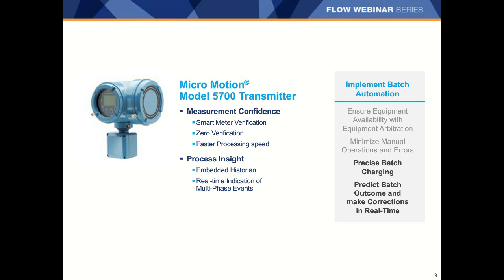The 5700 also offers faster, cleaner transmission of data. When milliseconds count in your fast control applications, signal speed and resolution are key. The 5700, that's the new high bar for providing the fastest response time and over 3 decades of knowledge in Coriolis signal processing to react quicker than ever in dynamic processes like batching and fluctuating conditions such as entrained gas.